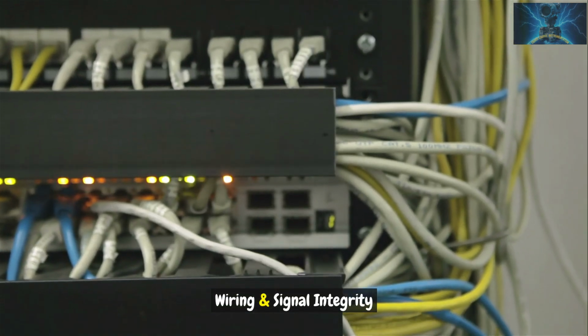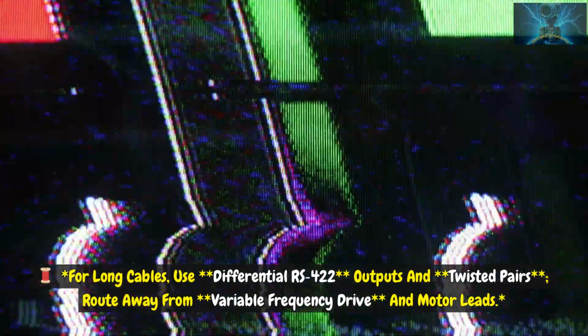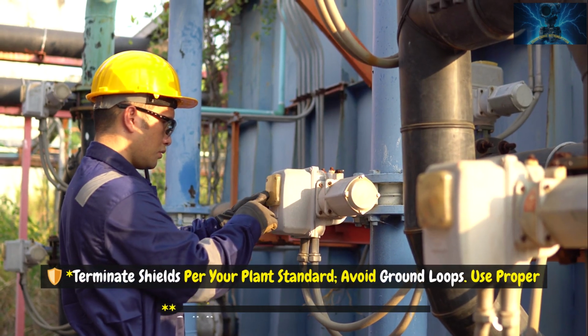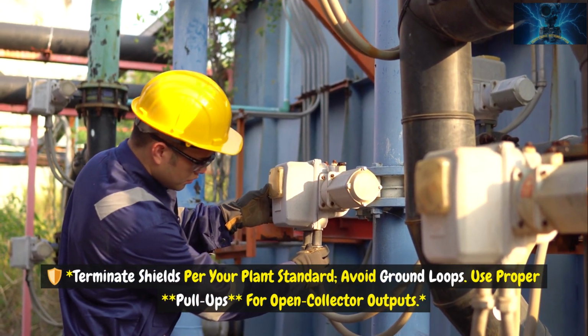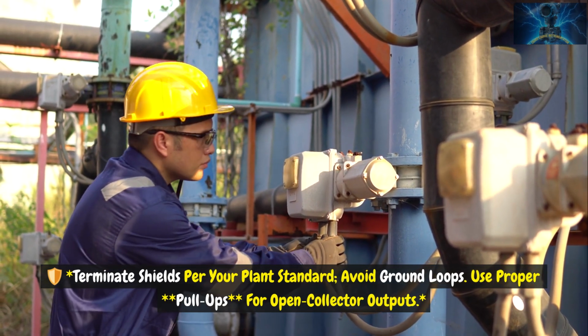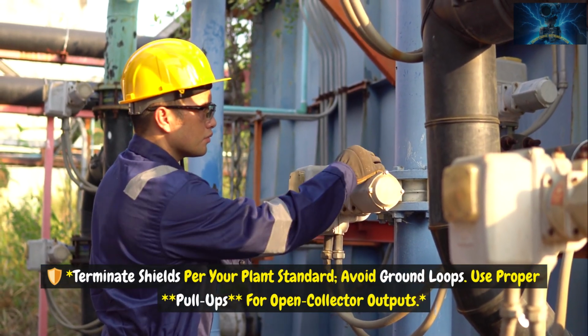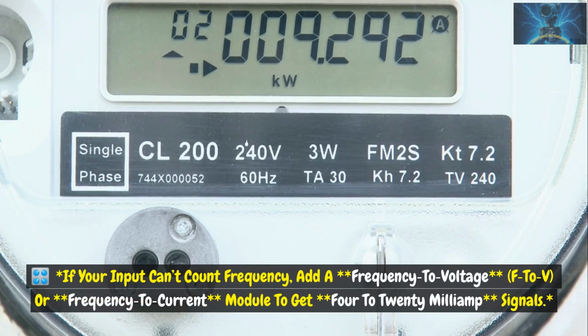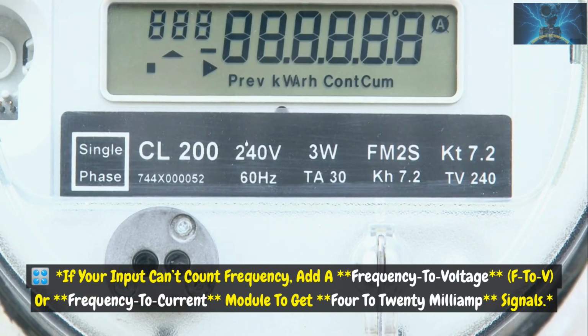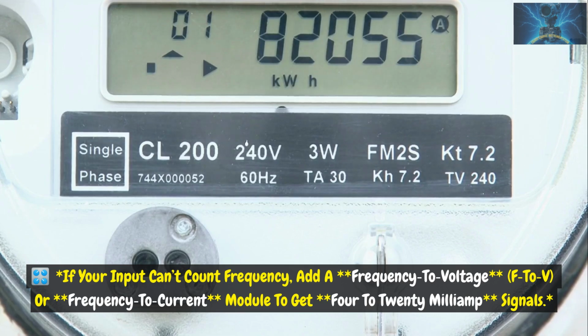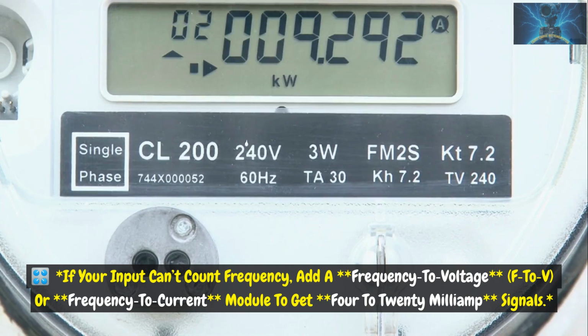Wiring and signal integrity. For long cables, use differential RS422 outputs and twisted pairs. Route away from variable frequency drive and motor leads. Terminate shields per your plant standard. Avoid ground loops. Use proper pull-ups for open collector outputs. If your input can't count frequency, add a frequency-to-voltage, F2V, or frequency-to-current module to get a 4 to 20 milliamp signal.